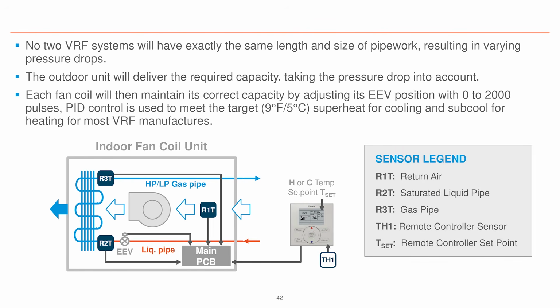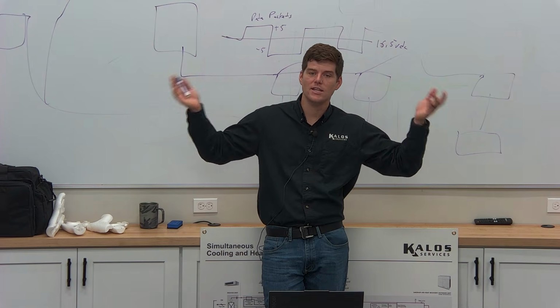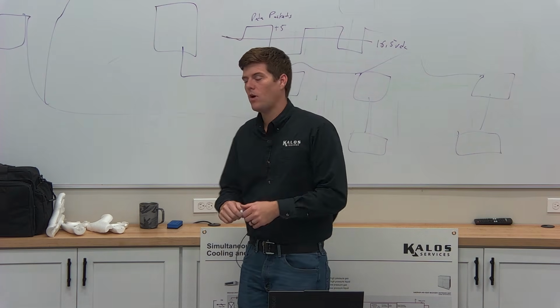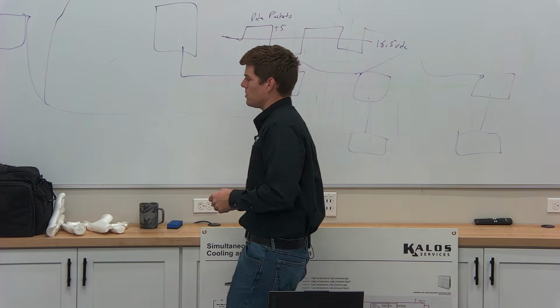Slowly wrapping up here is for what we look at. This is a typical indoor unit. There's a main PCB control board, right? That main PCB control board has 3 things. Every VRF piece of equipment usually has 3 things. Some just have 2. That's temperature in, temperature out. We measure temperature in and temperature out on every single VRF fan coil, whether it's Daikin, Mitsubishi, whatever. Why is that? Can anybody tell me why that is? Why do we need to know what temperature is coming in and what temperature is going out?